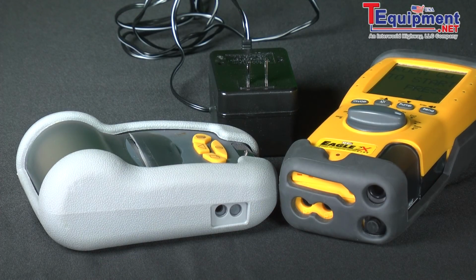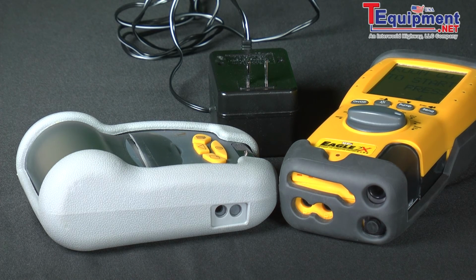One of the other items that we have, both the printer and the combustion analyzer use 4 AA batteries. If you want to use rechargeable nickel metal hydride batteries, you can, and each of these have a port and a transformer that you can use to charge them or to actually run them on the transformer. If I were doing a 30-minute CO room test, I would probably run it on the transformer rather than wear down my batteries.